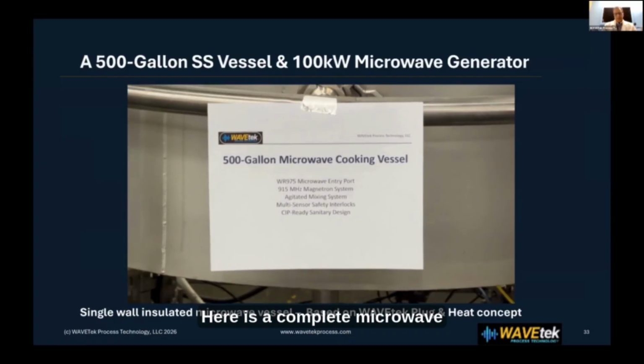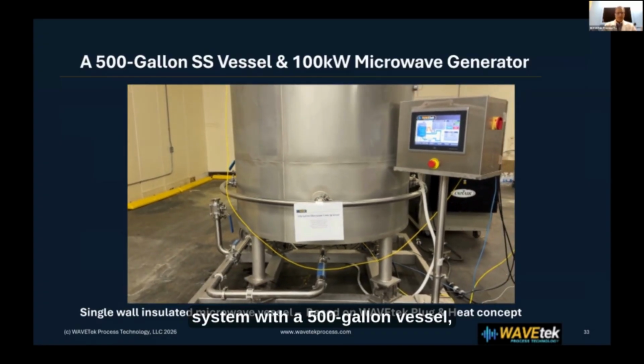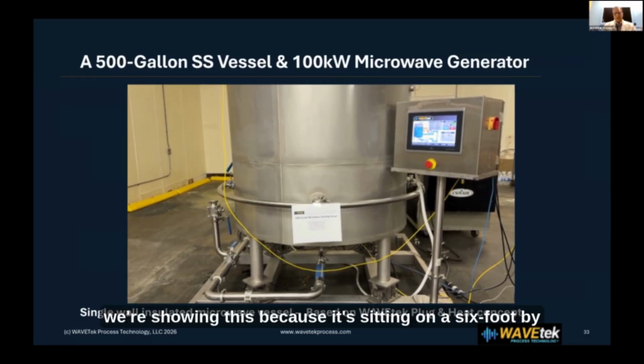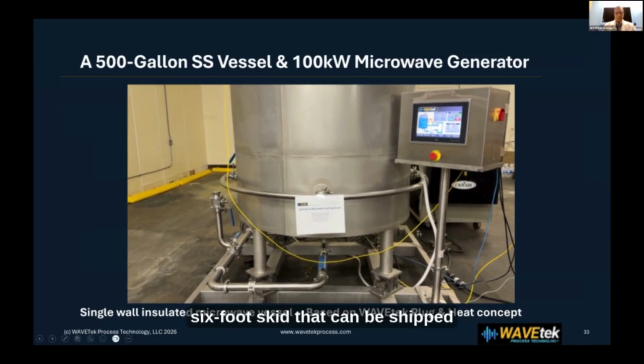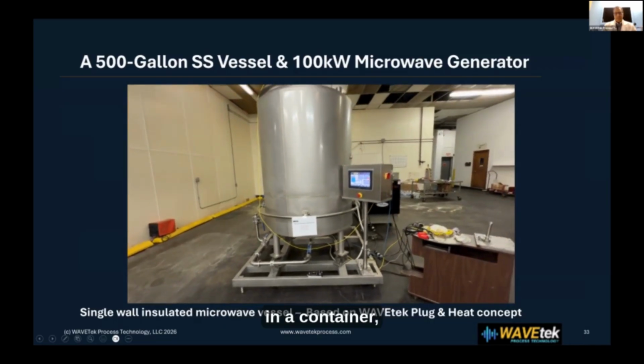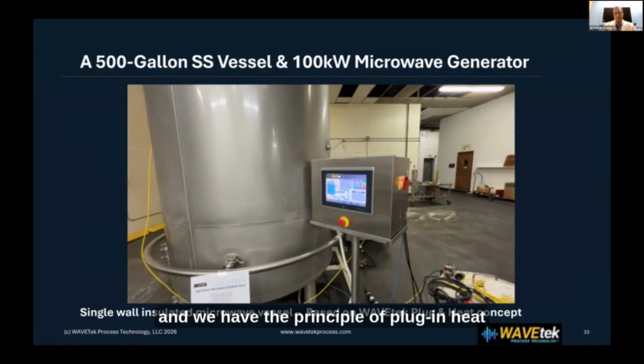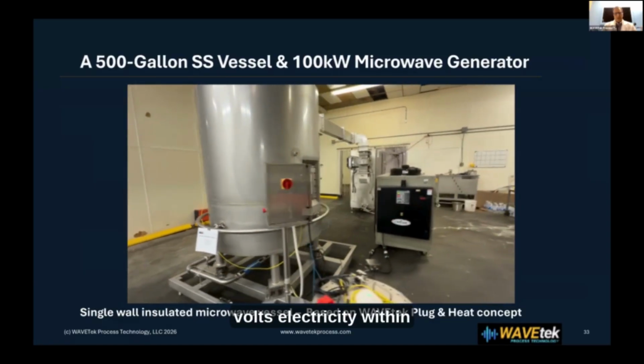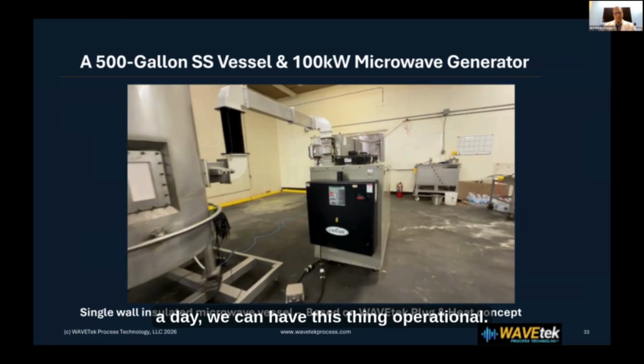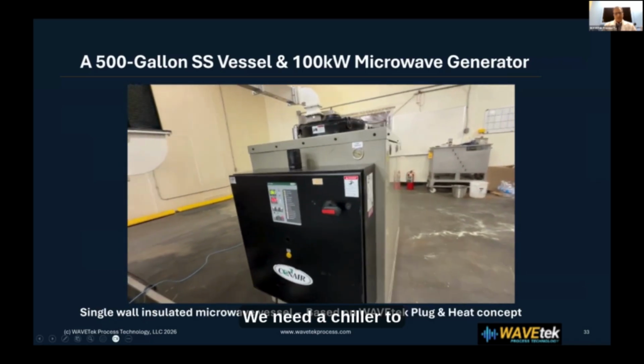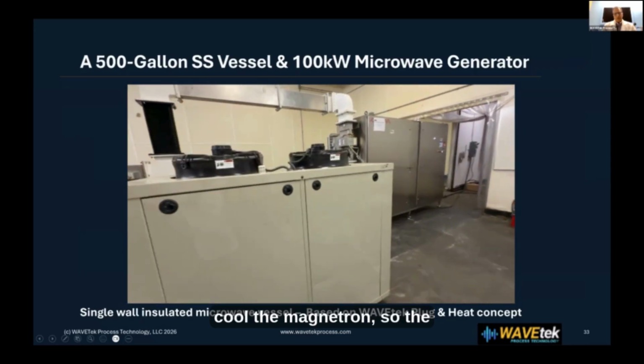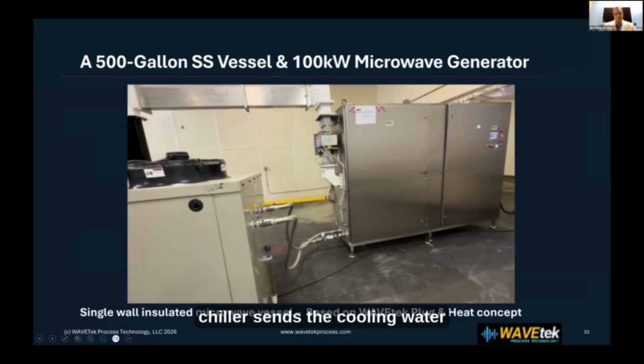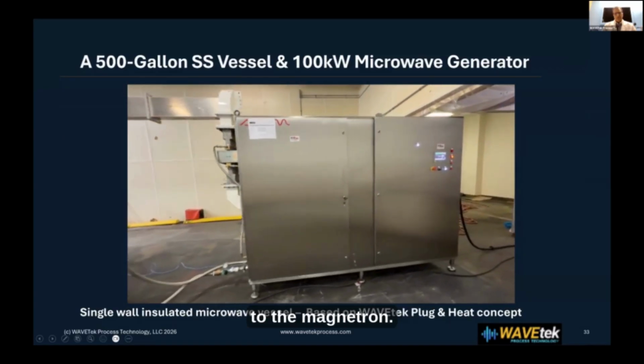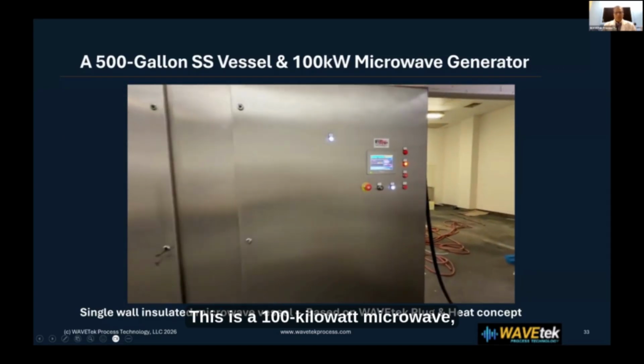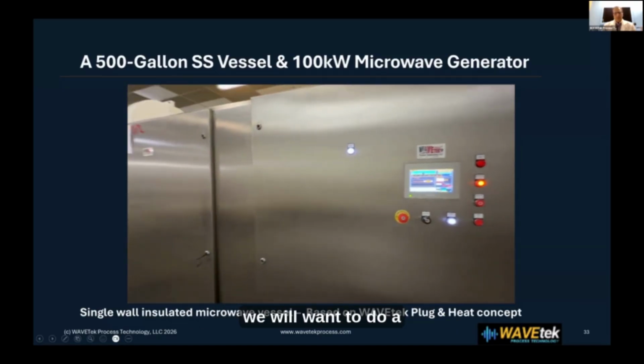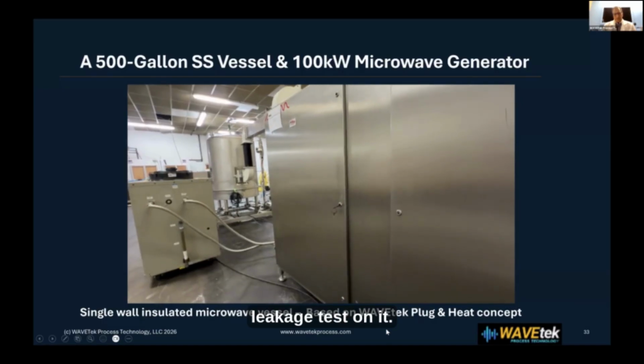magnetron. Here is a complete microwave system with a 500-gallon vessel. We're showing this because it's sitting on a 6-foot by 6-foot skid that can be shipped in a container. We have the principle of plug and heat, because once you get 480 volts of electricity, within a day we can have this thing operational. We need a chiller to cool the magnetron, so the chiller sends the cooling water to the magnetron. This is a 100 kilowatt microwave, and because it's on, we will want to do a leakage test on it.